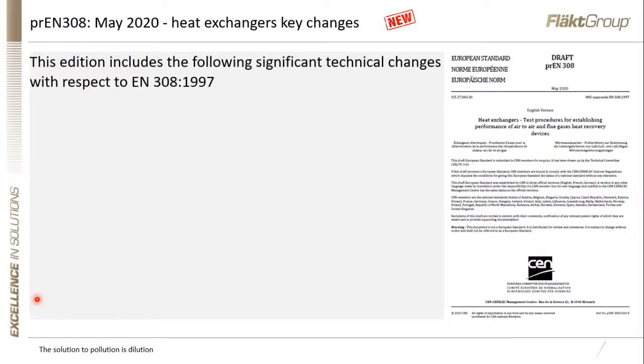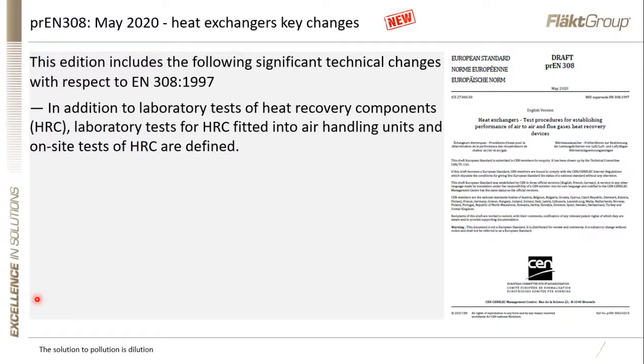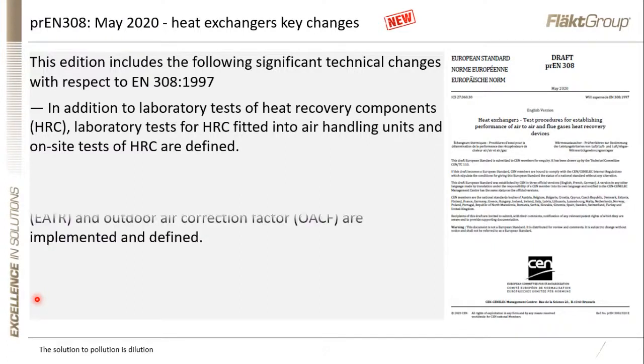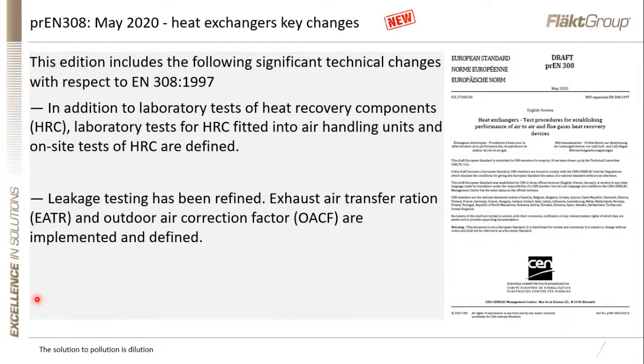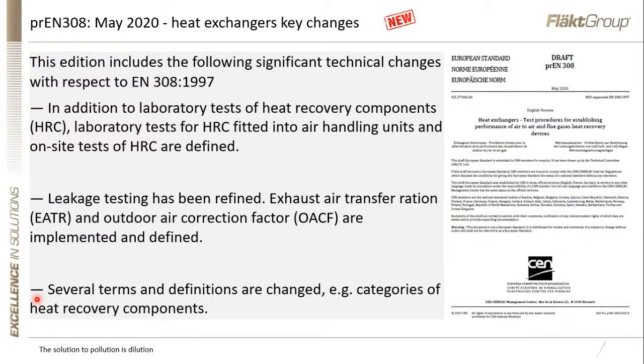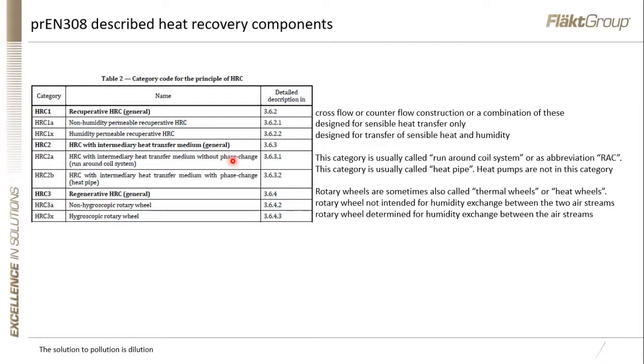So EN 308, it has some key changes. They are, in addition to laboratory tests of the heat recovery components, which is all that we had to do up until now, it will include laboratory tests for the heat recovery component, that's HRC, fitted into the air handling unit. You might find that it's a bit surprising that that wasn't the case before, but that's the reality. The effect of mounting the heat recovery component in the air handling unit was never tested previously. Leakage testing has been refined. EATR and OACF are implemented and defined. So in other words, the testing that we have to do to establish the EATR in principle is defined now within the standard. And several terms and definitions have changed, e.g. categories of heat recovery components, and I'll come on to that in a moment. So all heat recovery components are now defined.